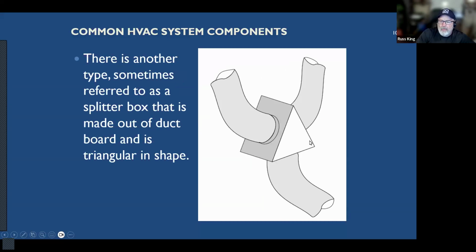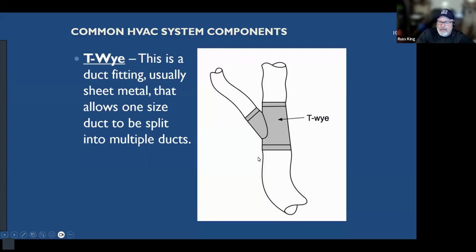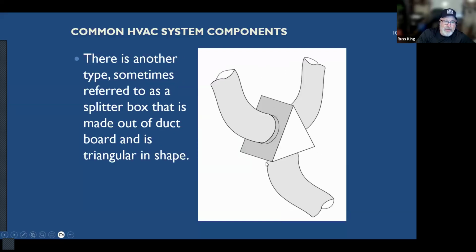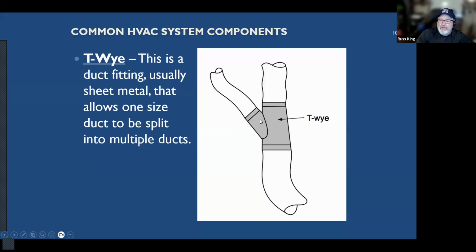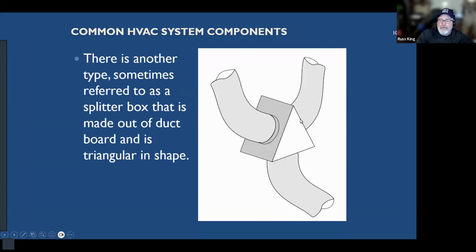Another fairly common way to do that is instead of this sheet metal fitting like this, they'll have these ductboard wedges. We call them cheese wedges, like a Green Bay Packer cheese hat. Okay. The problem with these is the air gets very turbulent inside. So there's a lot of resistance to airflow. But the reason some contractors like these is because they're basically made on site. Whereas these, you have to order these and you have to bring out the right sizes. So you might have like a 10 by 7 T-wye, and you've got to buy the right one and you have to have the right one on hand in order to install those ducts. But these, you bring out these cheese boxes and you cut whatever size holes you need and you put a start collar in there to run the ducts out.